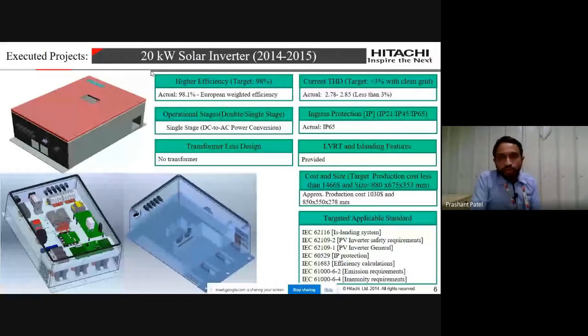As it's a rooftop application, IP65 is always the desired rating, so we built our solar inverter based on IP65. Based on the new grid code formed by the Indian government, we had to provide the islanding feature in the 20 kilowatt solar inverter. So we provided LVRT and islanding features, and the size and cost are according to the market. The approximate BOM cost for the 20 kilowatt solar inverter is about 60,000 INR, and all the applicable standards we considered are mentioned here.